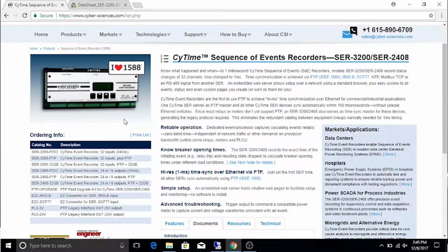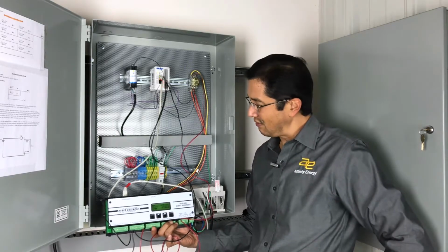particular test scenario. The SER is actually being synchronized using the internet time. We don't have a GPS clock here in our facility, so we've connected up our sequence of events recorder to use that as basis for time. And then we've wired three inputs to a PLC so that we could generate some changes of state in order to record that.